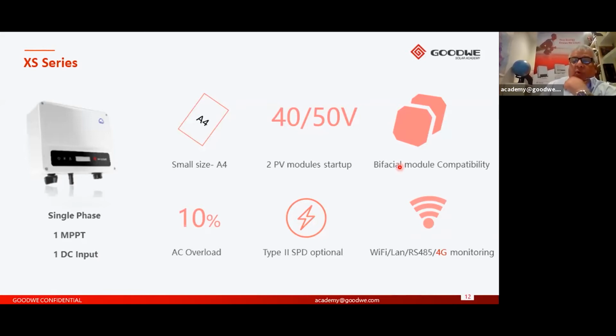You'll hear me talk a lot about bifacial module compatibility. Currently the majority of panel manufacturers are bringing more and more bifacial modules into the market - these produce a higher input current. Our inverters are compatible with bifacial modules throughout the range, able to accept the higher input current and work very efficiently. Even though it's small, lightweight and compact, you get 10% extra power from the AC side. In some markets we may need type 2 surge protection, which can be added if requested as an optional extra.